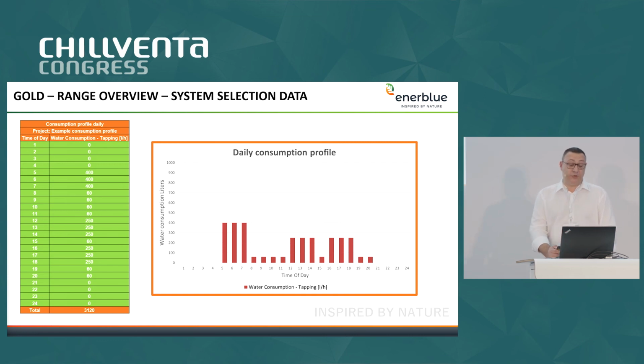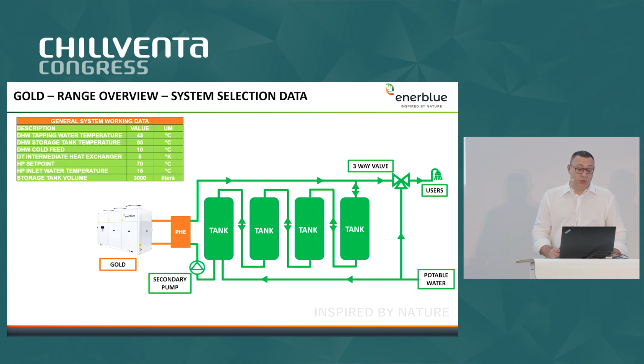And for system characteristics, for sure, we need to know the daily water consumption for the application in order to identify the peaks and the other daily consumption hours. In addition to this, we also need to know the temperatures inside the circuit. So the tapping water temperature, that is near the users, for example, the temperature the customer wants to have inside the storage tank, the temperature of the cold feed water from the city water, of course the intermediate heat exchanger delta T, and the set point for the heat pump. So we need several pieces of information in order to size the right system for this application.